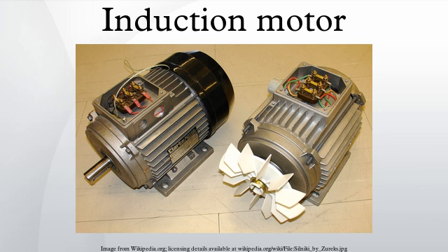Since rotation at synchronous speed would result in no induced rotor current, an induction motor always operates slower than synchronous speed. The difference, or slip, between actual and synchronous speed varies from about 0.5 to 5.0% for standard design B torque curve induction motors. The induction machine's essential character is that it is created solely by induction instead of being separately excited as in synchronous or DC machines or being self-magnetized as in permanent magnet motors.